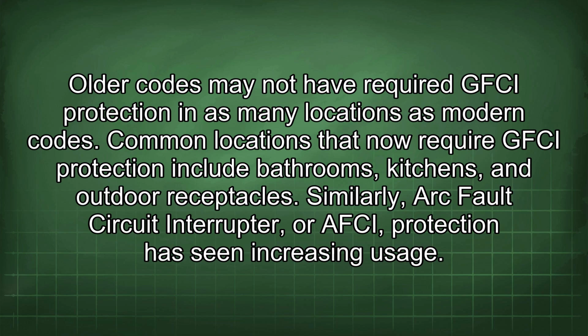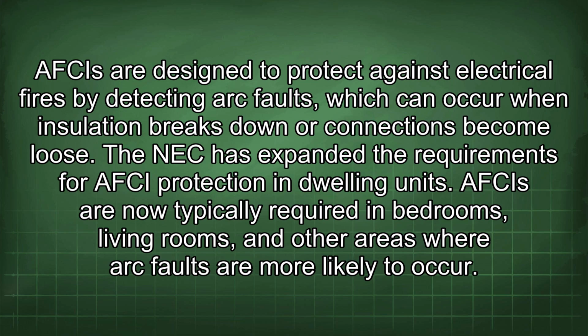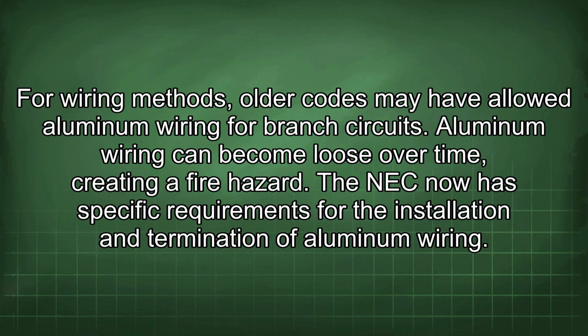Similarly, arc fault circuit interrupter, or AFCI, protection has seen increasing usage. AFCIs are designed to protect against electrical fires by detecting arc faults, which can occur when insulation breaks down or connections become loose. The NEC has expanded the requirements for AFCI protection in dwelling units. AFCIs are now typically required in bedrooms, living rooms, and other areas where arc faults are more likely to occur. For wiring methods, older codes may have allowed aluminum wiring for branch circuits. Aluminum wiring can become loose over time, creating a fire hazard. The NEC now has specific requirements for the installation and termination of aluminum wiring.